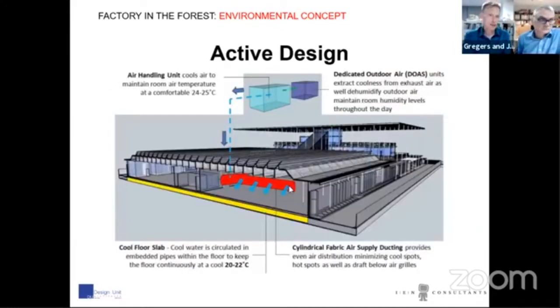On the active design, in addition to the floor slab cooling, which delivers a third of the cooling, we had a normal air conditioning system, except we used a dedicated outdoor air system which did all the dehumidification. Once that was done, a normal air handling unit would top up only the sensible cooling if additional temperature adjustment was needed.